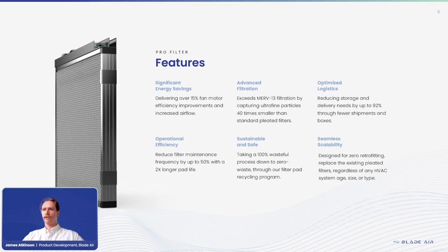So the metal mesh, that frame, is reusable, and you only swap out the media when it is time to change. So you're sending much less to landfill. You also have a much easier time with the maintenance itself because you don't have to lug a huge box of cardboard filters up to the roof. They're just vacuum sealed filter pads that you swap out. You can put the old filter into the bag from the new one and not have to store several pallets worth of filters.